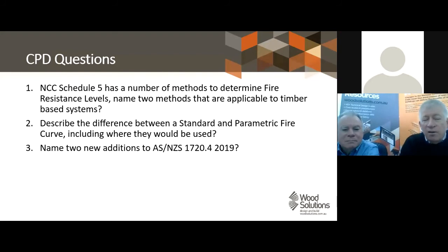You need to do a standard fire test to get that data. And our favourite standard fire tests, I'd like to get $1 every time that was mentioned today. So unfortunately, you need to use real data for that. And remember that plasterboard is not the only system you can use. You could be using a fabric such as a TBA 5-ply fabric, or it could be an intumescent coating or something like that. So there are different ways of achieving that, but that would have to be based on the standard fire curve again.